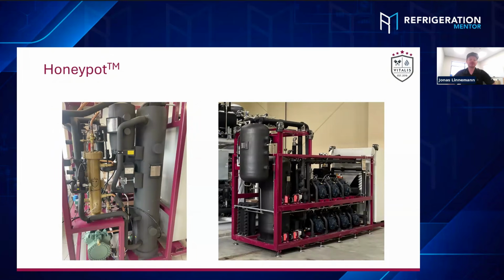And it's always good to do a loop check before you start that system up, to make sure that if the regulators or the differential pressure switch from the compressor is triggering an alarm, it actually shuts the compressor off, right? That's a general pre-checkup of the entire safety system. That's highly recommended. But once that's done and the system starts up and operates for the first hours, it's always good to have a look at how the oil is refilling, if there's a lot of foam showing up inside the glasses or not, and also if you see some changed color of the oil.